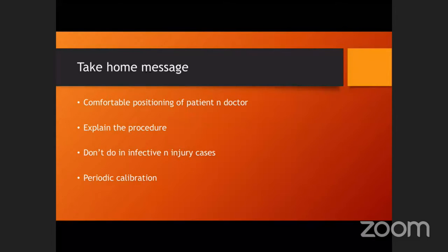So my take home message would be, before taking this IOP, we have to have a comfortable positioning of the patient and doctor. The procedure should be explained well to the patient. We must not do it in infective cases or in injury cases, and a periodic calibration of the Goldmann applanation tonometer is a must to have an accurate result.